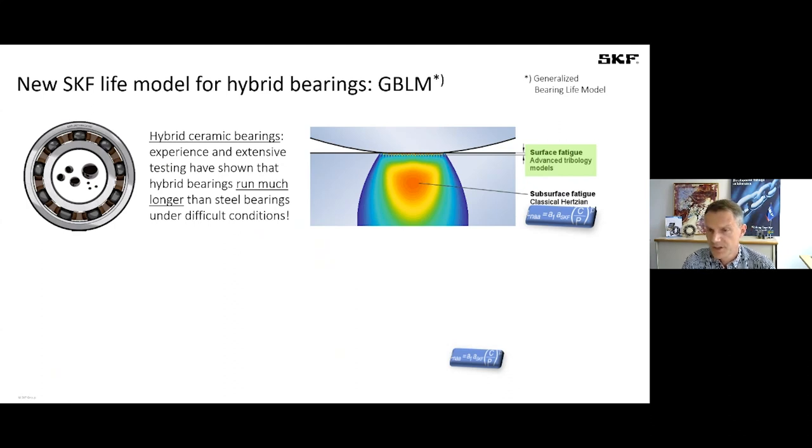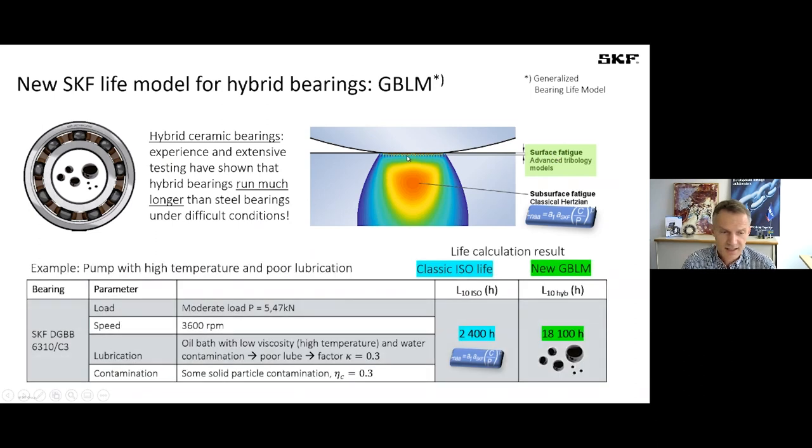And it's out there, it's in our tools, the tools I mentioned before. And it's taking into account not only the classical Hertzian subsurface fatigue, but the surface damage that can happen if you have very poor lubrication conditions. And just as an example here, without going into the numbers, for a tough case where bearing life according to the classic theory might be only 2400 hours when you calculate it, if you use the new life theory and you use hybrid bearings and you apply the data, you end up with a multiple of this classic life. And this is data that is verified by a lot of experiments and testing.